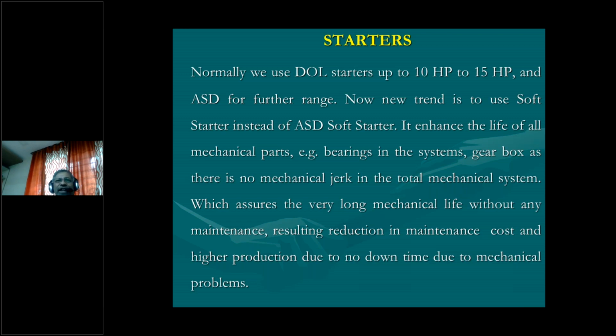But considering that, heating gets generated in the motors. So different types of motors are used. Many times I came across cases where they changed to VFD with the same motor, and then started complaining that the motor burned twice the time because the motor is getting overheated. So just keep it in mind, for VFD application, selection of the motor is also totally different. The bearings are insulated bearings, so it is magnetically cut.